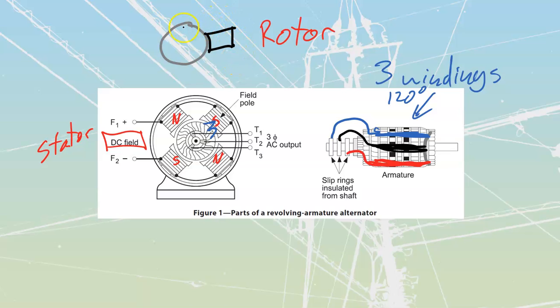A commutator switches, but this maintains contact continuously. If we draw the shaft of the alternator looking at it from the end, the shaft has a groove along it called the keyway. Further inside, our conductors come through and attach to the inside of the slip ring. The slip ring itself is mounted on a plastic or ceramic base that insulates it from the shaft itself.